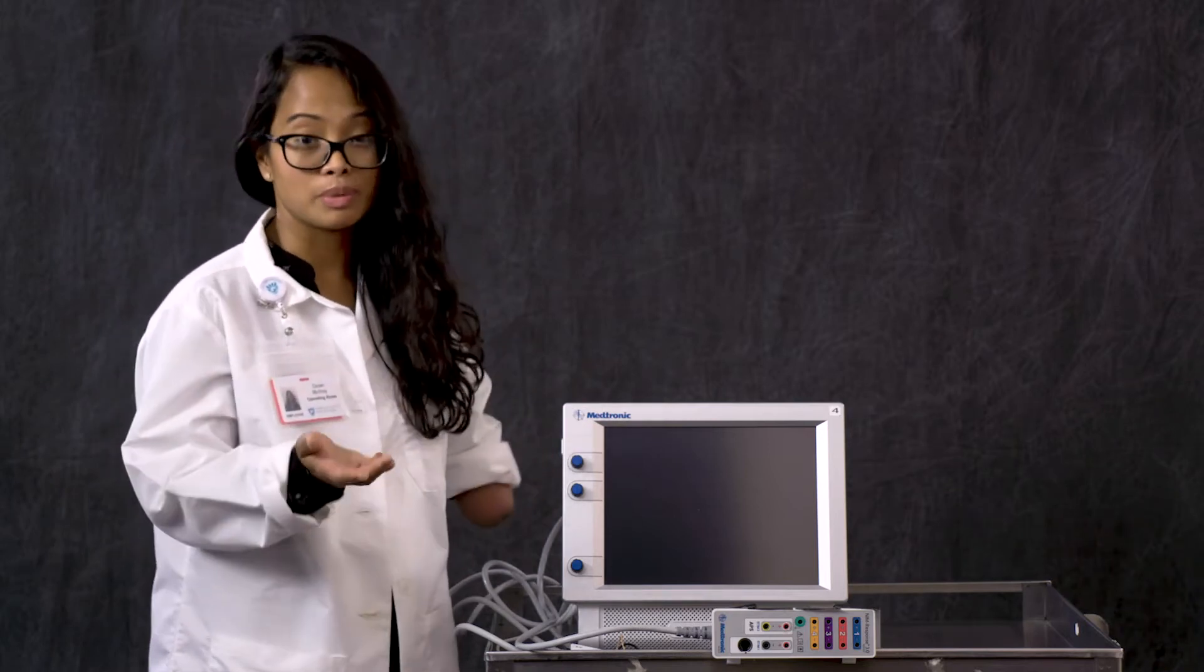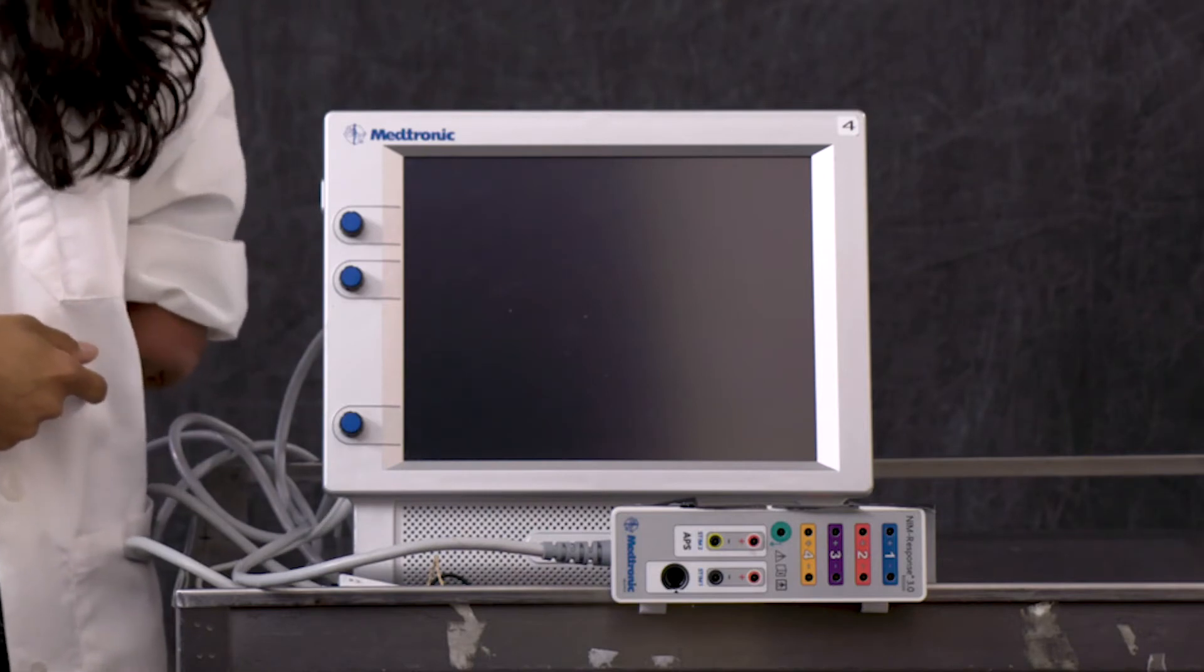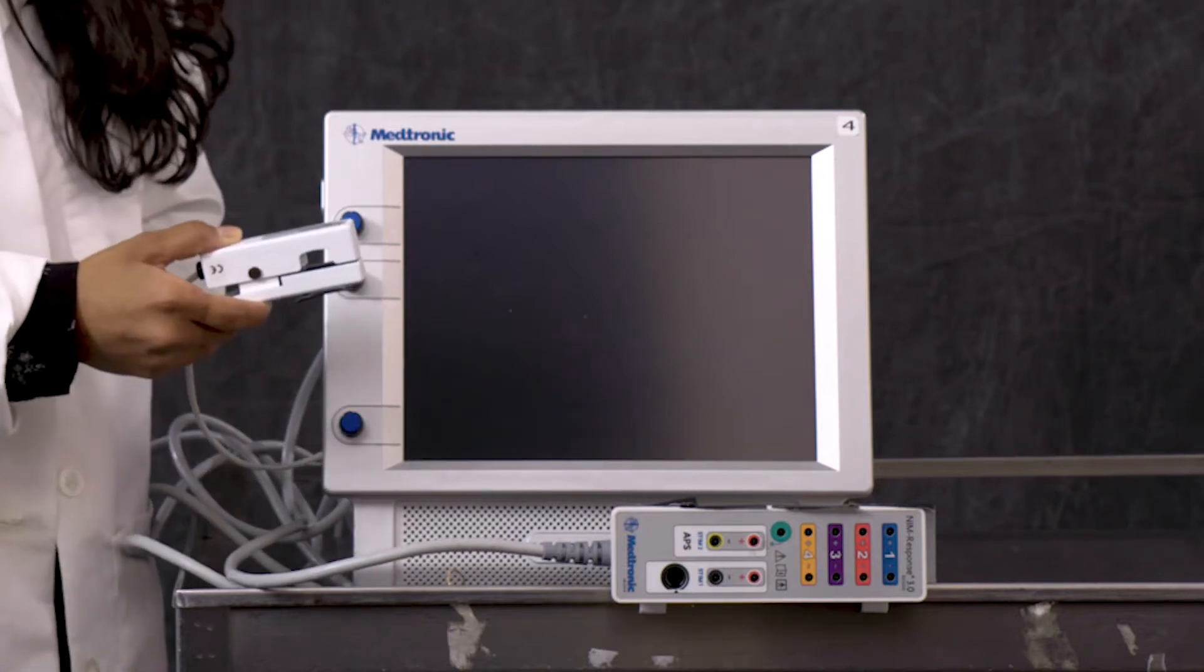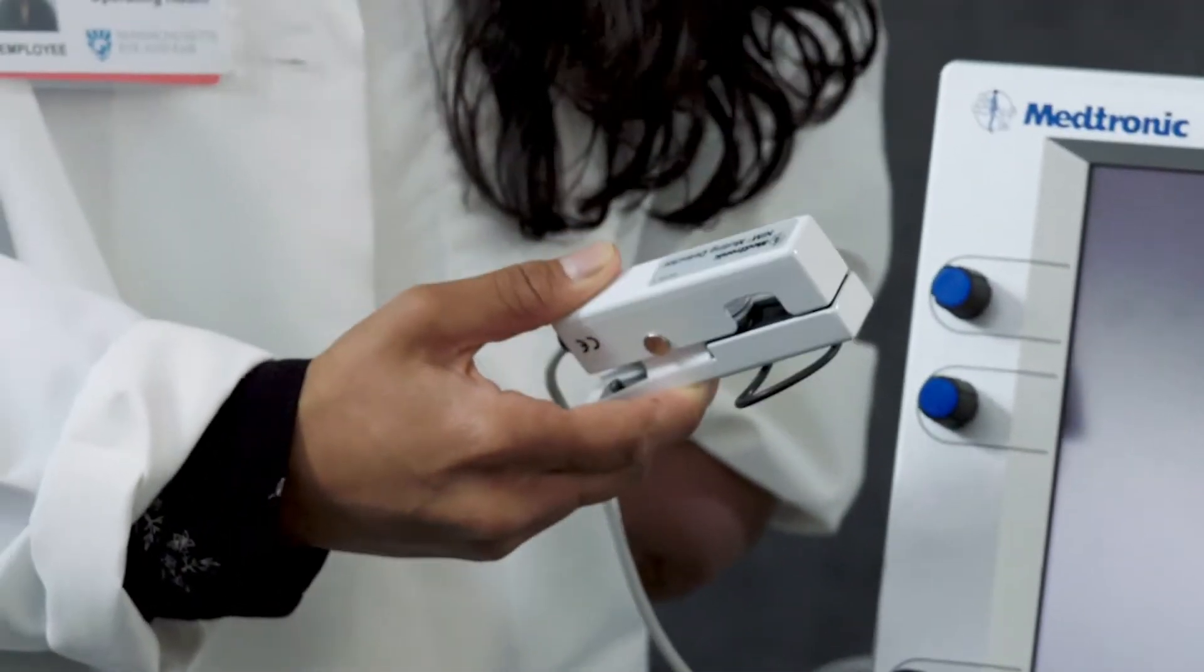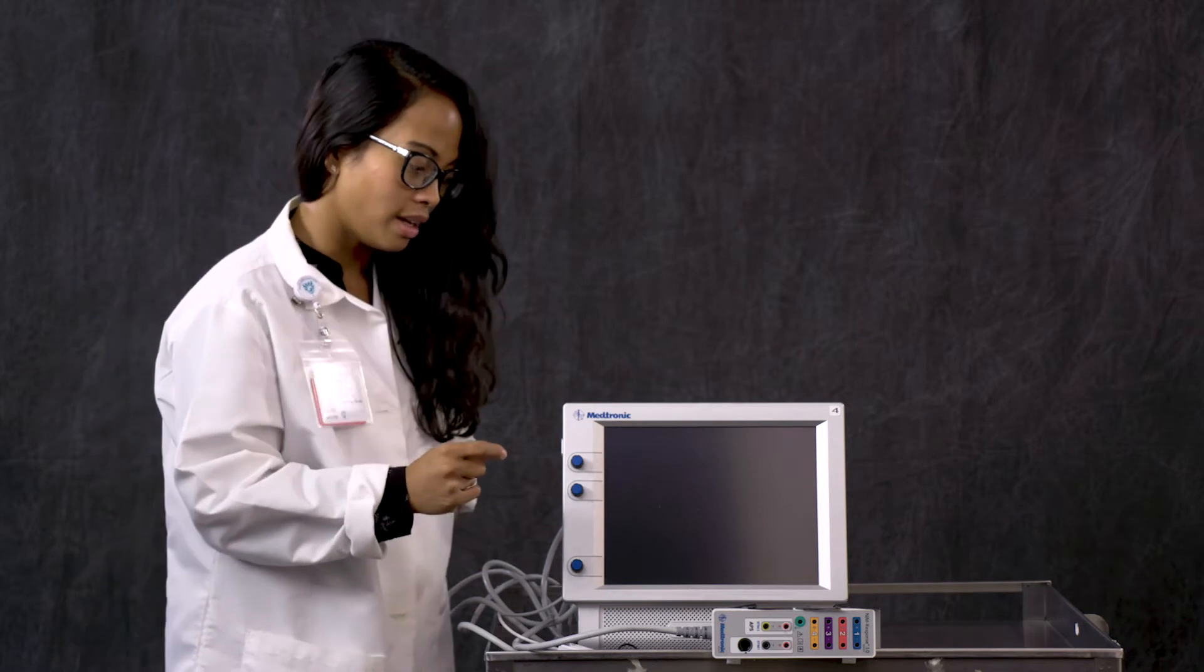The three main things that we need would be our EMG console sponsored by Medtronic, a patient interface cable box where the electrodes plug in, and our muting detector probe or cable. This wraps around the electrocautery during surgery and mutes all that electrical noise or artifacts. It makes things a lot easier.